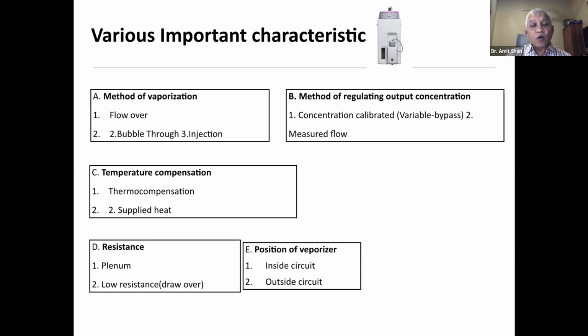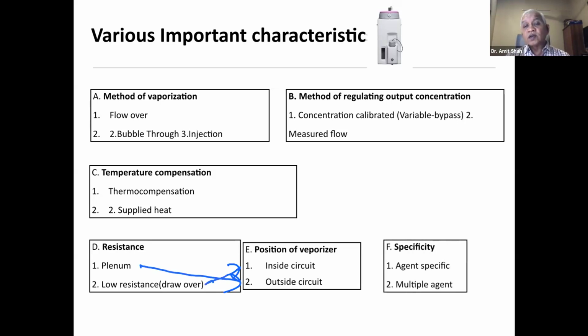So a plenum or higher resistance vaporizer will be required not in the circuit, but in the anesthesia machines. While most of the low resistance ones can be inside the circuit, like our ambu bag or any other anesthesia circuit where you don't have anesthesia machines which give you a pressurized gas. And of course, some of them are agent specific; the older versions were used for multiple agents also. But for safety purposes, we want agent specific.